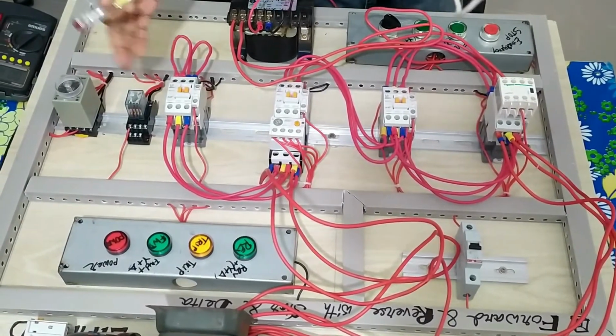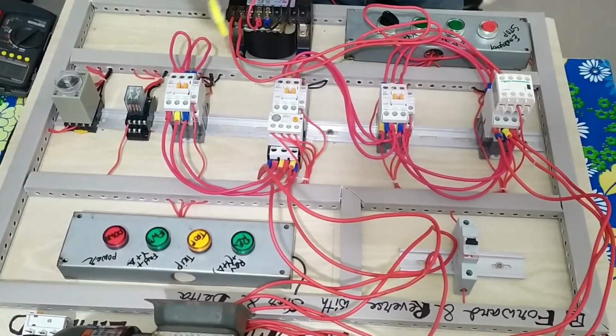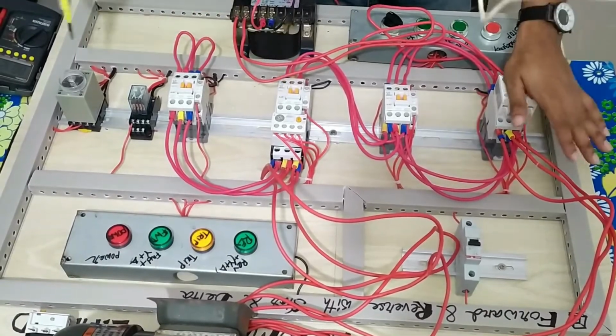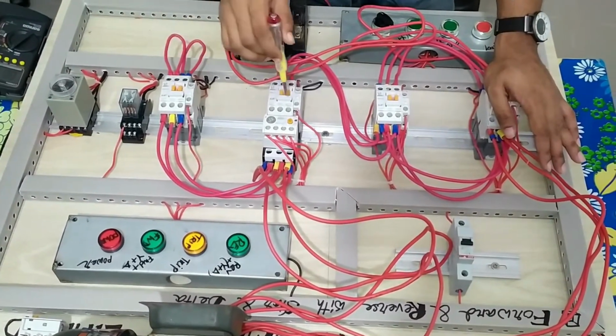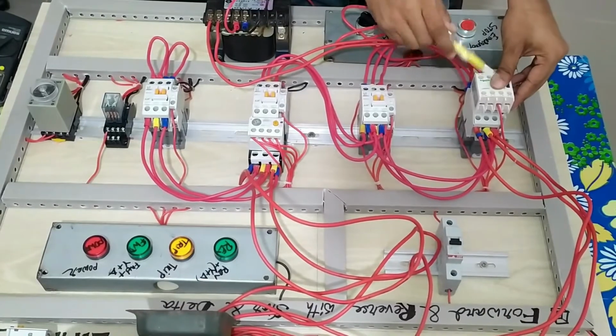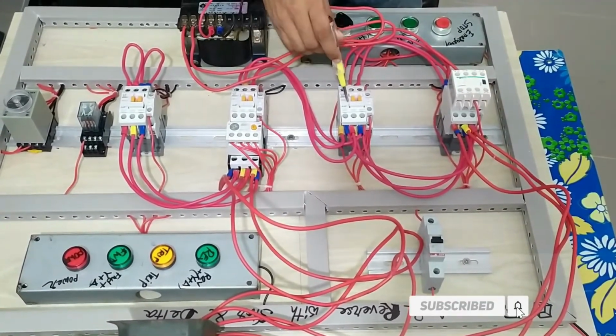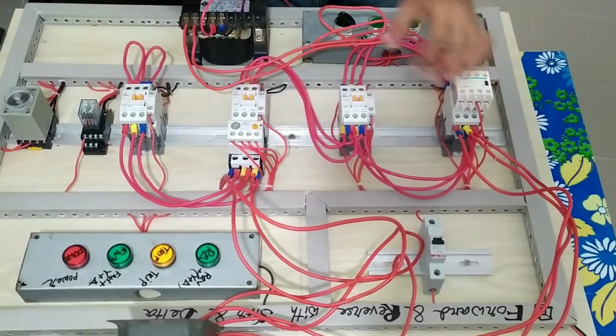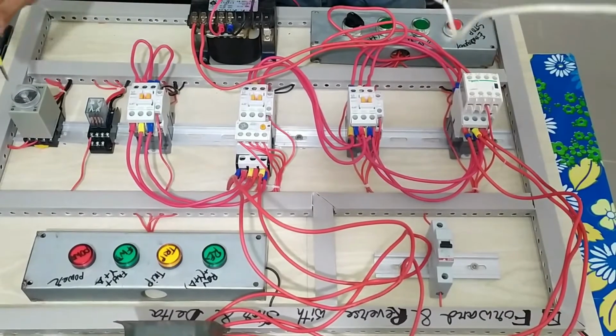This is the conversion of direction, the motor starting in star. After 20 seconds it's converted to delta for forward direction, and when we run the motor in reverse, it also goes to star directly, and after 20 seconds it's converted to delta.